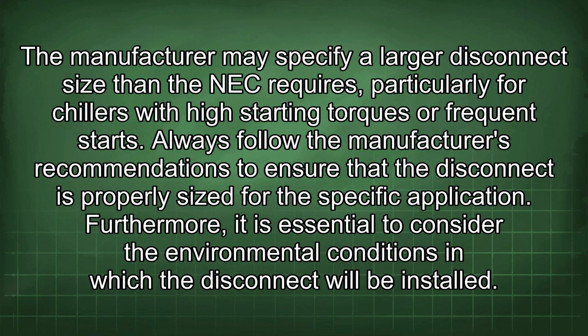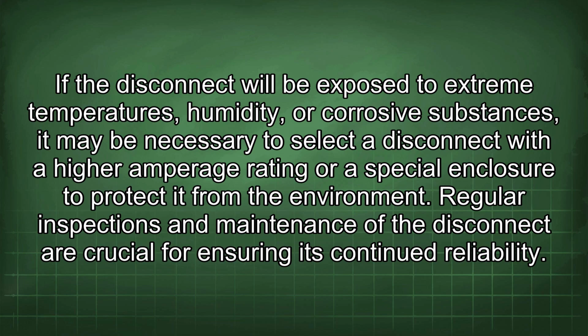Furthermore, it is essential to consider the environmental conditions in which the disconnect will be installed. If the disconnect will be exposed to extreme temperatures, humidity, or corrosive substances, it may be necessary to select a disconnect with a higher amperage rating or a special enclosure to protect it from the environment.